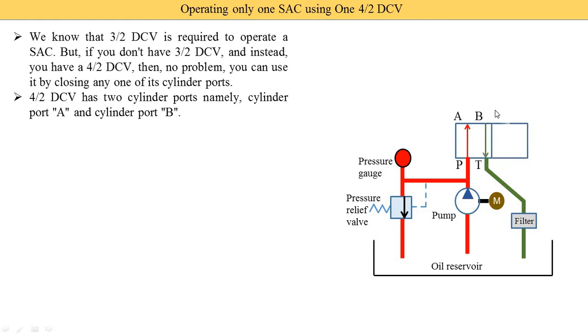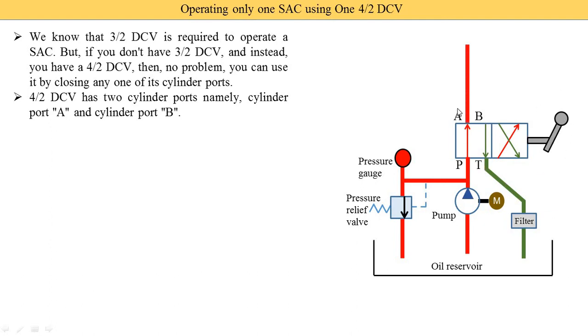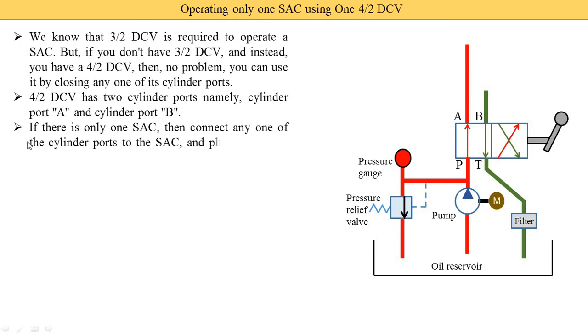Here you see the second position. In the second position there are 4 ports: port P is connected with B, port A is connected with T. This directional control valve is operated by using a manual lever. Here you see one outlet from port A and the second outlet from port B. Out of these two, if there is only one single acting cylinder, connect any one of the cylinder ports to the single acting cylinder and plug the other cylinder port.